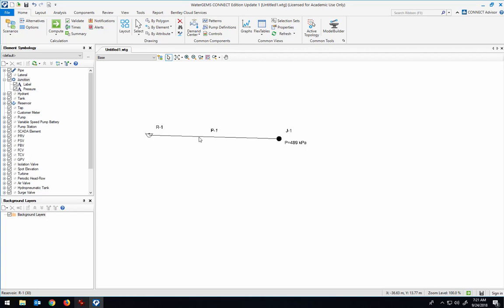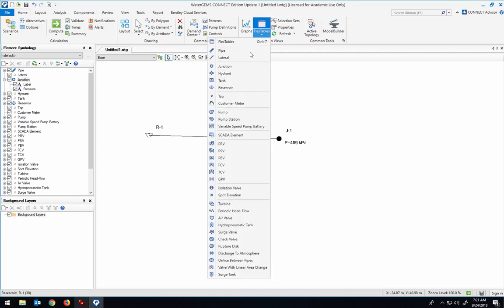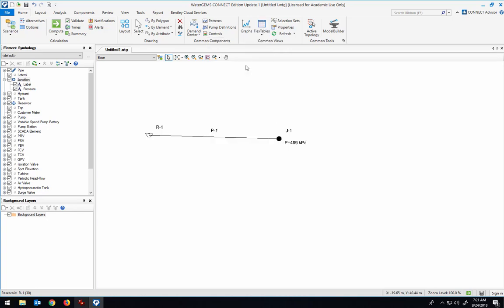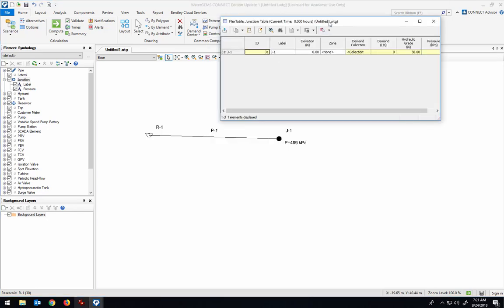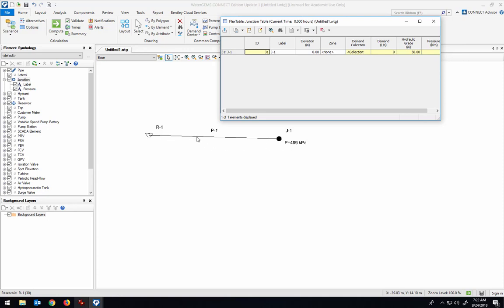But when water starts to flow through this pipe, the pressure should go down. And the way that we can say that water is flowing through the pipe is to open up the junction table, and inside the junction there's a column heading called Demand Collection. That's where you're specifying how much water is flowing out of that junction. So if I say that 10 liters per second is going out of the junction, then the system will automatically assume that it's coming from the reservoir and going through the pipe to get to the junction.